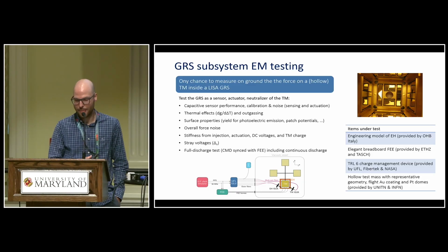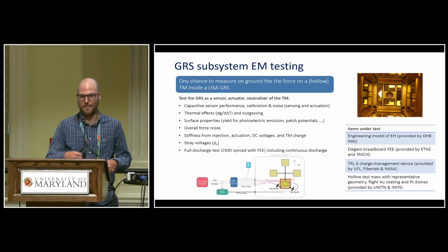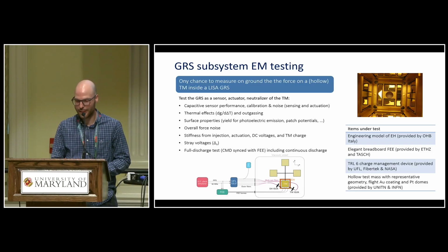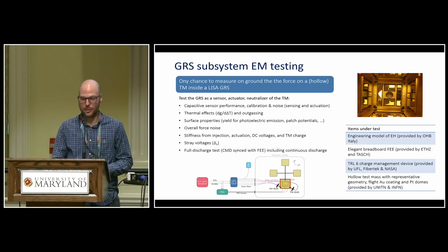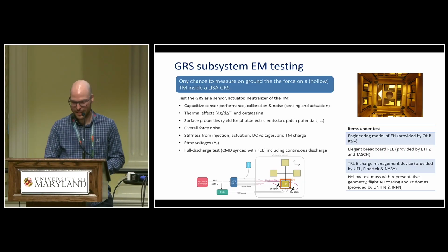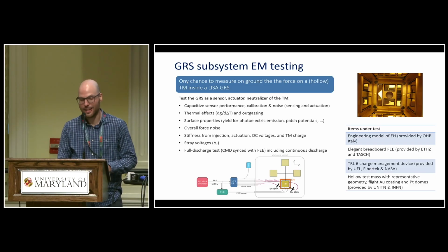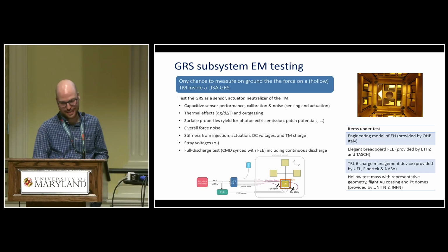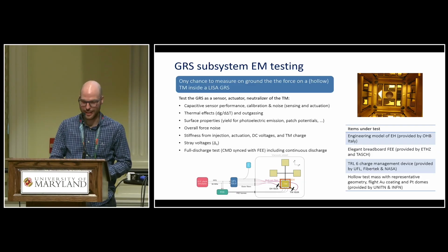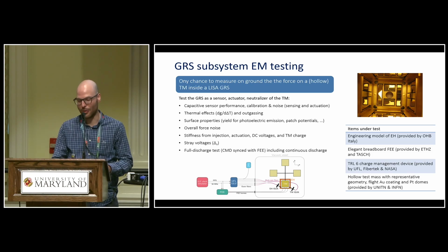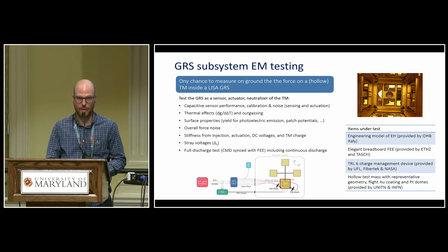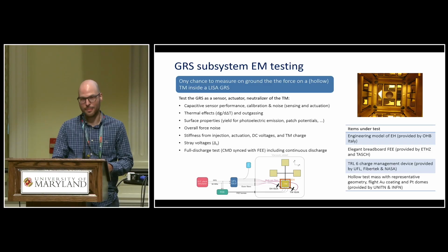GRS subsystem testing with torsion pendulums is very important because it's the only chance that we have to measure on ground the forces acting on a hollow test mass in the LISA GRS, and it encompasses several tests. Here I show you some of the tests that we can do. For example, we test the performance of the capacitive sensor in terms of sensing, actuation noise, and calibration. We can measure thermal effects. We can measure the surface properties of the test mass and the electrode housing, for example photoelectric yield, patch potential, and so on.